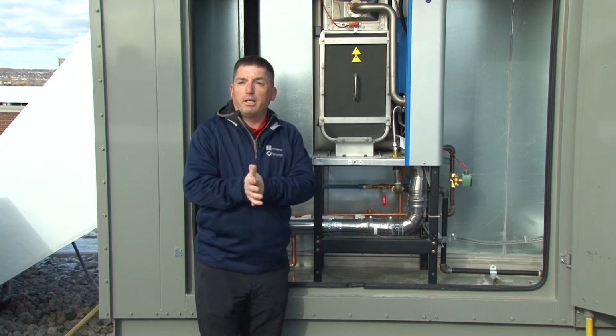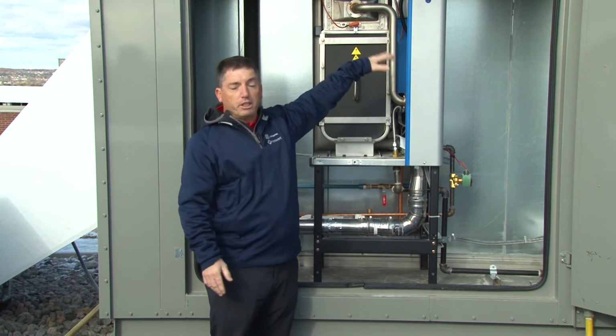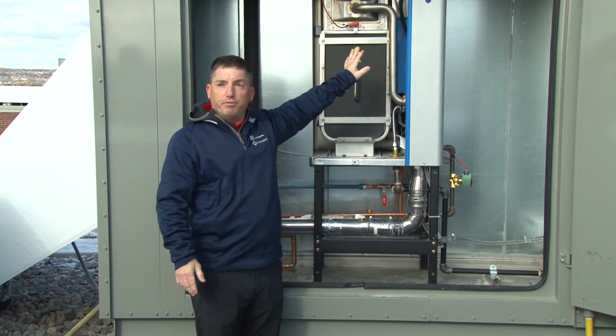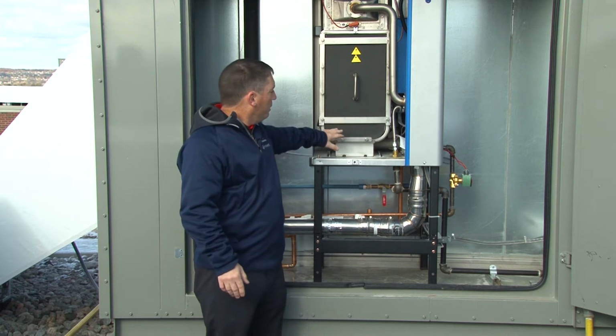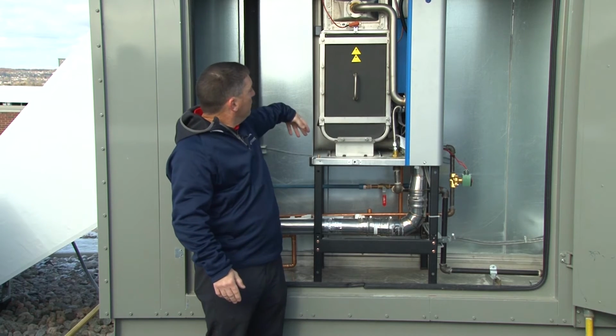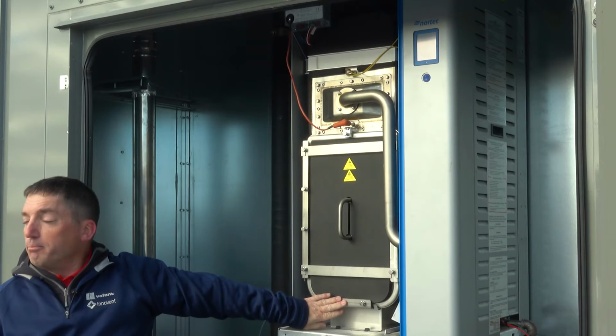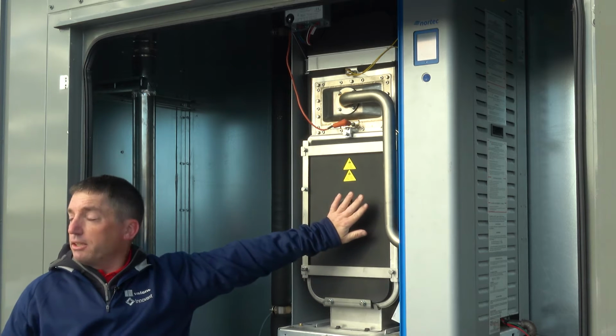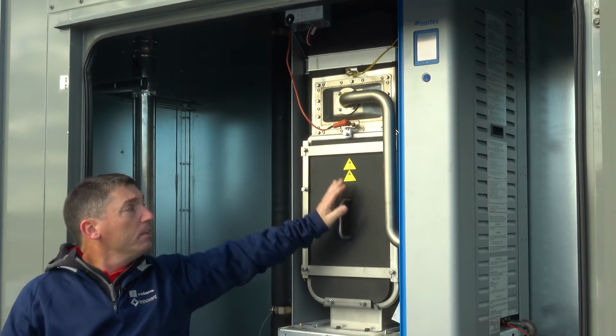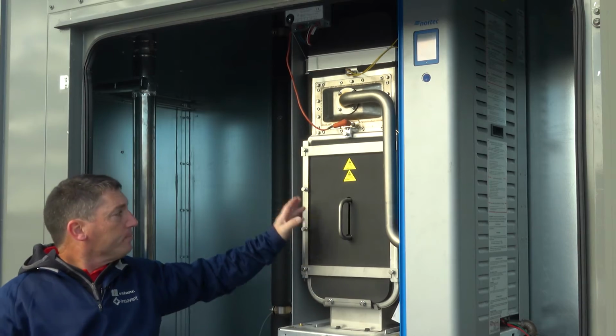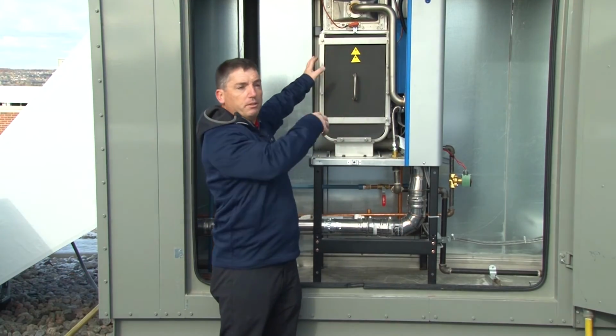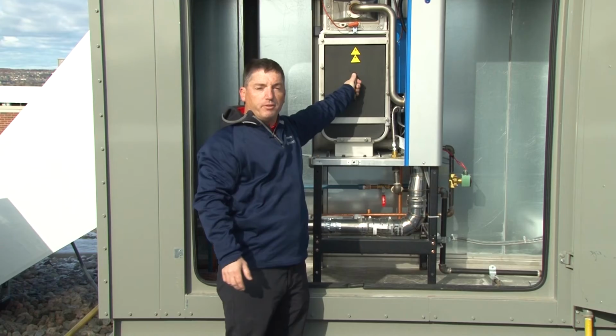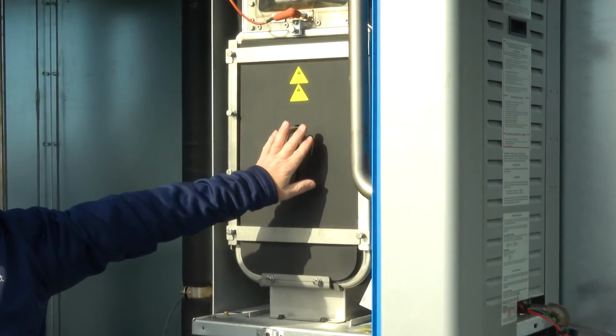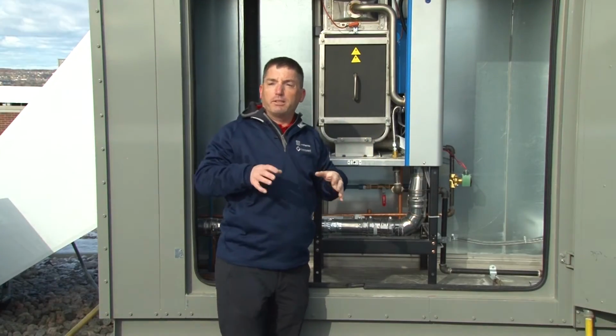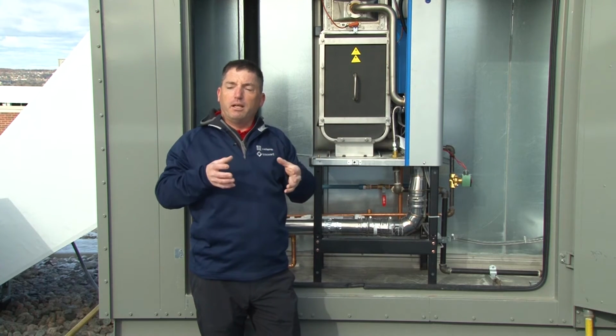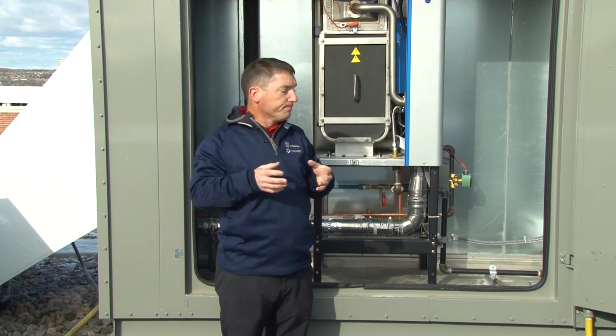So when it does come time to clean it, you're going to shut the unit down, do a full tank drain, and then we have 13 bolts here that keep this access panel secure to the tank. Loosen those bolts. You're going to remove the two bars, which will let the two side bars come off, and then you can open this access panel, which is going to give you access to the interior of the tank and the exterior of the heat exchanger.